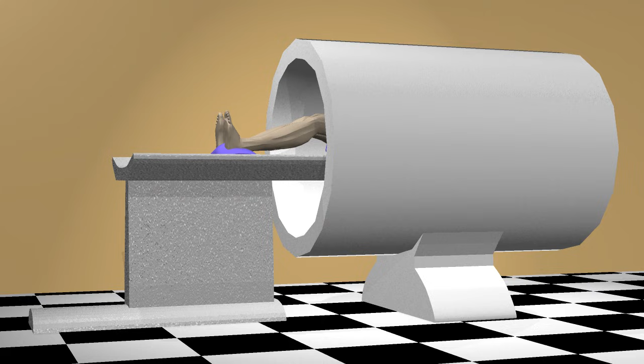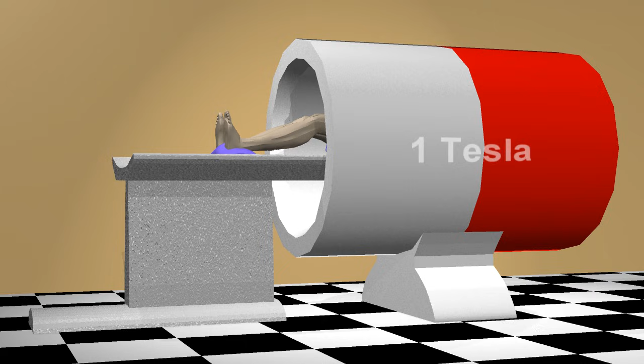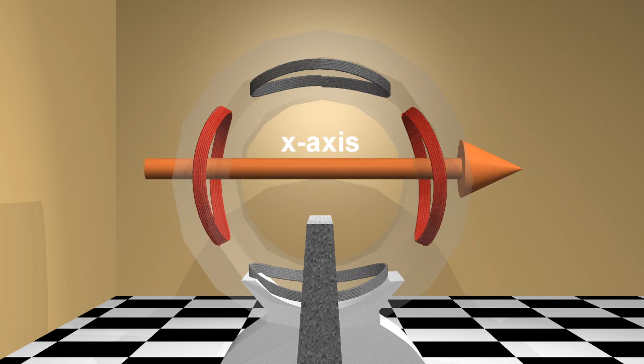When we first get into the MRI machine, a superconducting magnet creates a near homogeneous magnetic field from one side to the other that determines the strength of the MRI machine. Common systems are 1, 1.5, and 3 Tesla in strength. There are 3 sets of gradient magnets in the MRI used to localize locations in 3D space: the Z-axis, X-axis, and Y-axis.